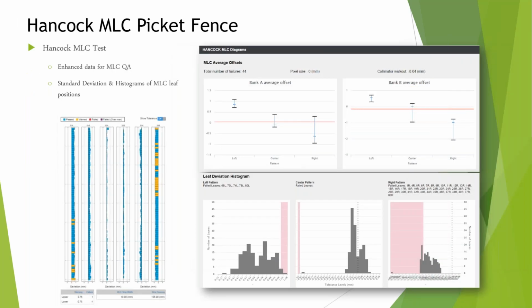On the Elekta machine, we all have the Hancock MLC picket fence test, which takes an image of half the field at a time, two separate images, and stitches them together and gives you an analysis of each leaf position. This turned out to be pretty handy when we were commissioning the system and validated our MLC offset in the Ray Station system.